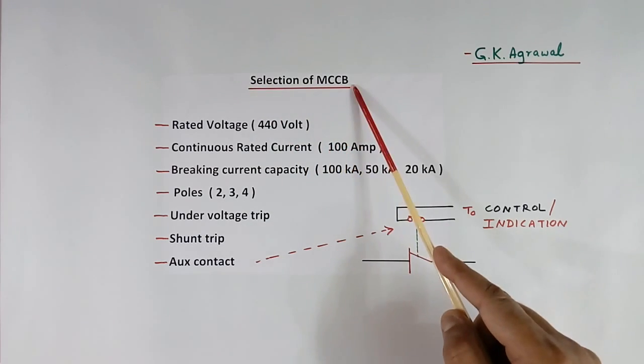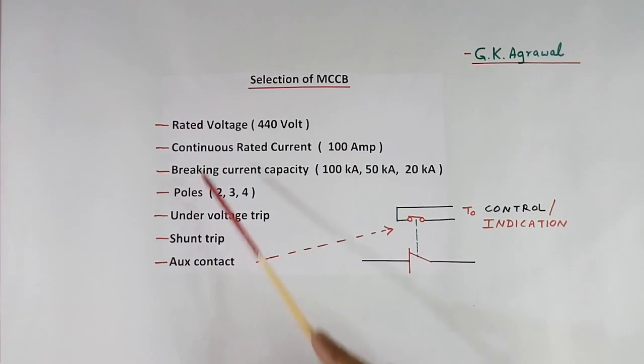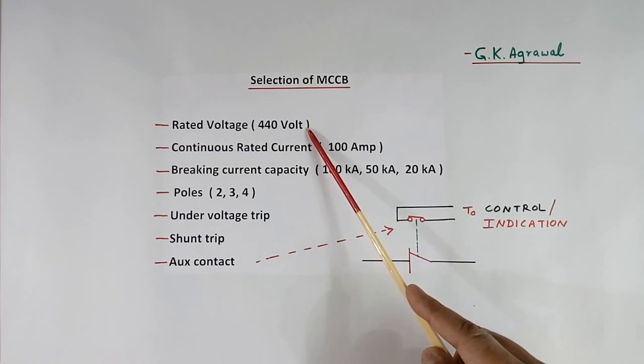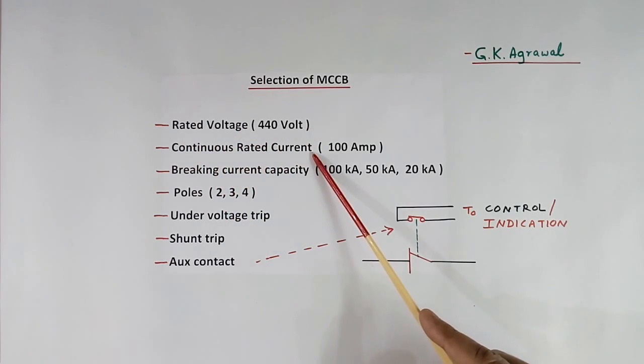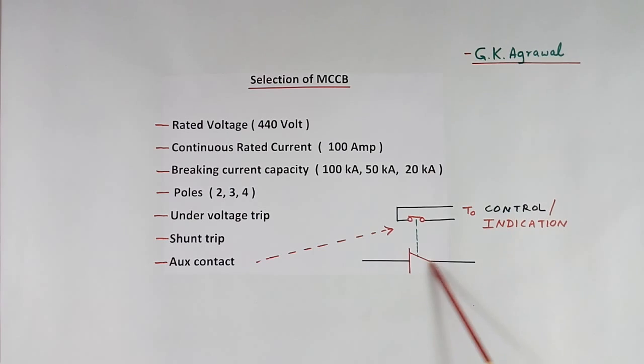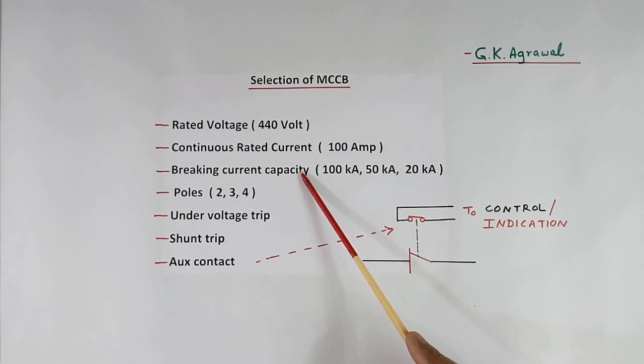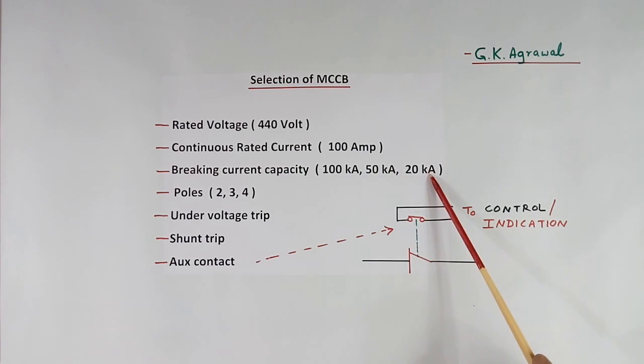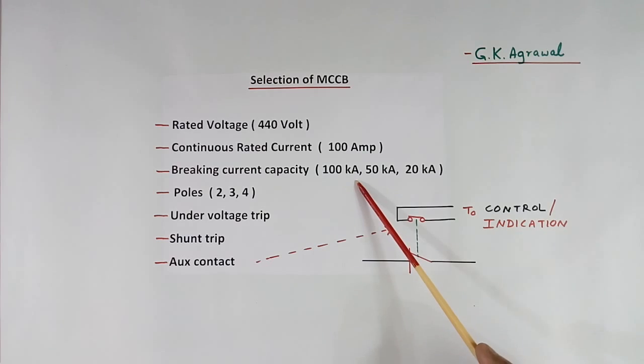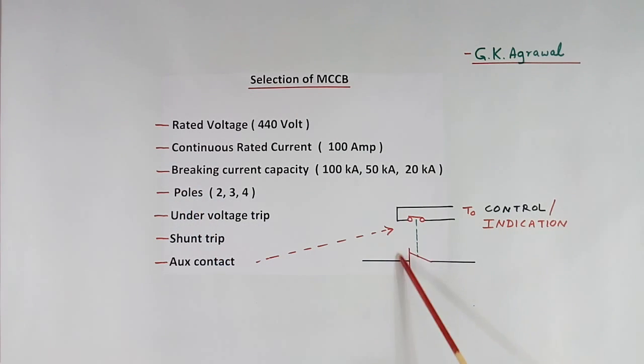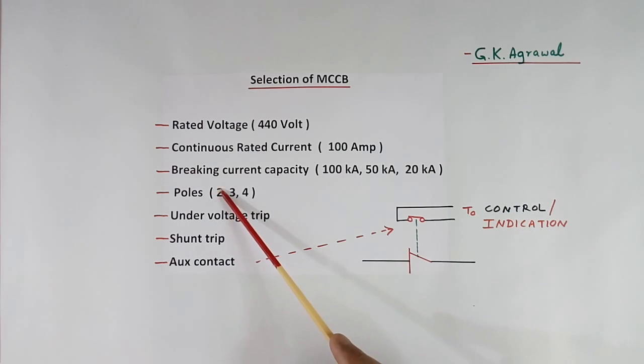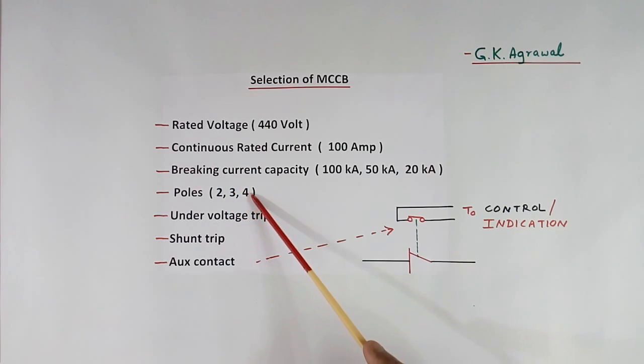When we want to select an MCCB, we should know: the rated voltage, say 440 volt; the continuous rated current, say 100 ampere — this rated current means whatever maximum continuous current will flow in this contact; the breaking current capacity, which may be 20 kA, 50 kA, or 100 kA; and how many poles are required. If it is single phase with line and neutral, there will be 2 poles. If it is 3 phase, there will be 3 poles. If 3 phase including neutral, there will be 4 poles.